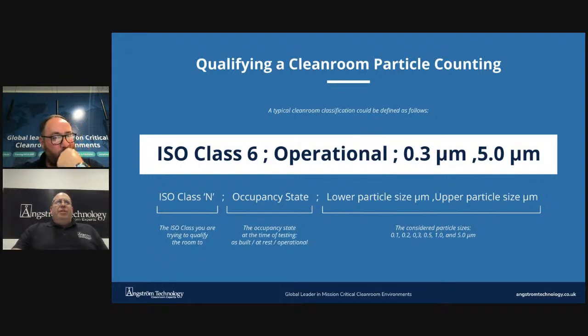This is often a measurement used to make sure ventilation systems and filters are working properly. It is what the room is capable of achieving now that you have been using it. Finally, operational. This means that you are measuring the air quality during the normal course of the day whilst the room is occupied, with people doing things and moving around. This is usually the dirtiest time since people provide most of the airborne particulate and stir up particulate from surfaces.